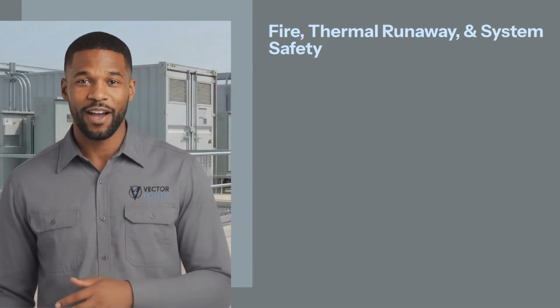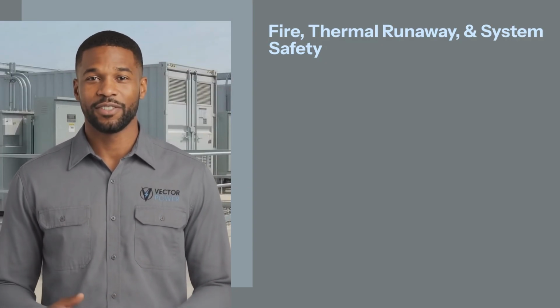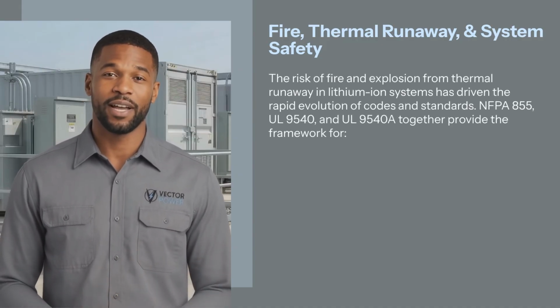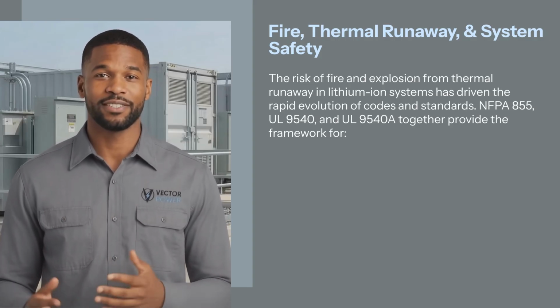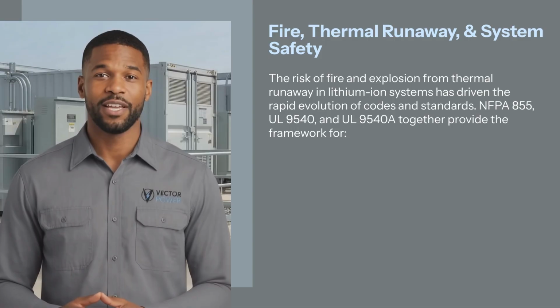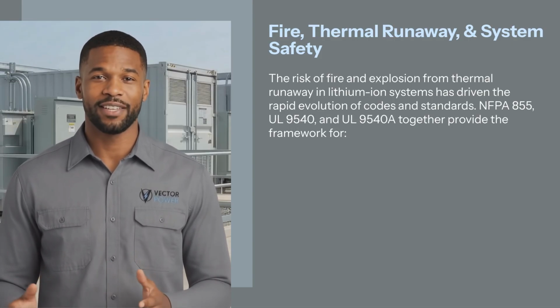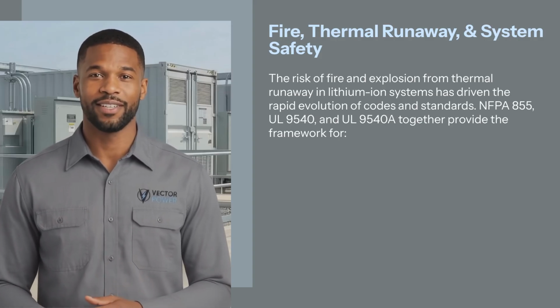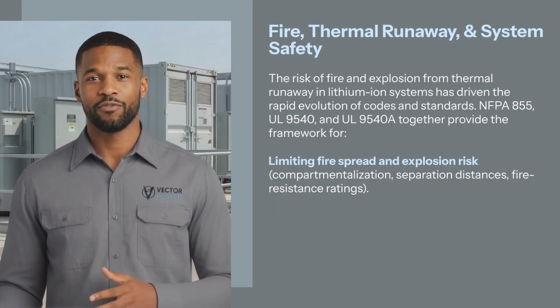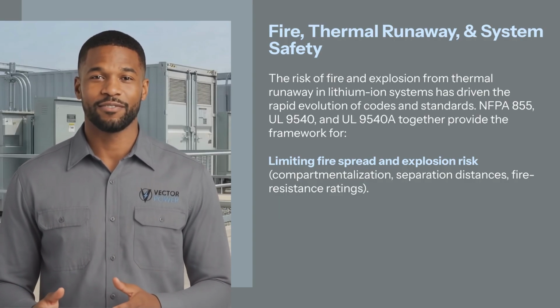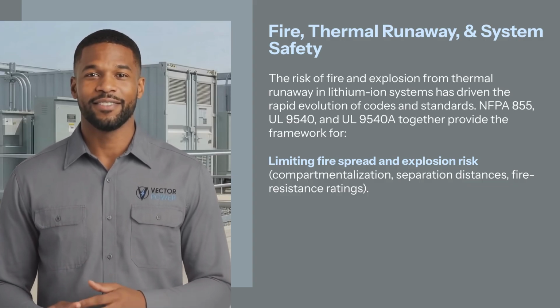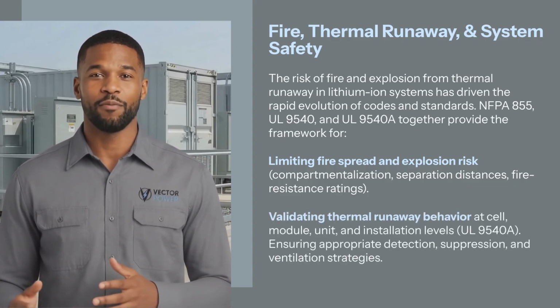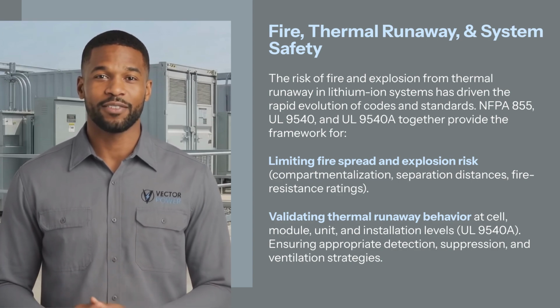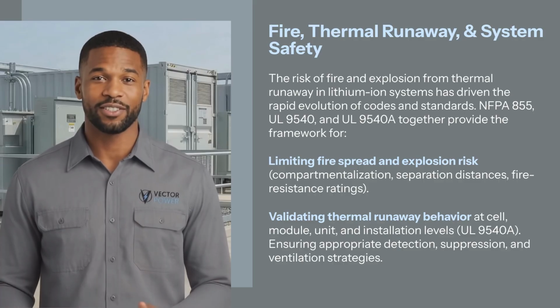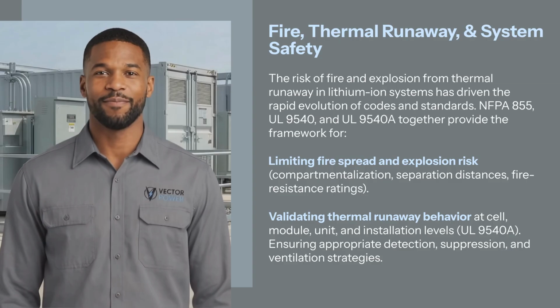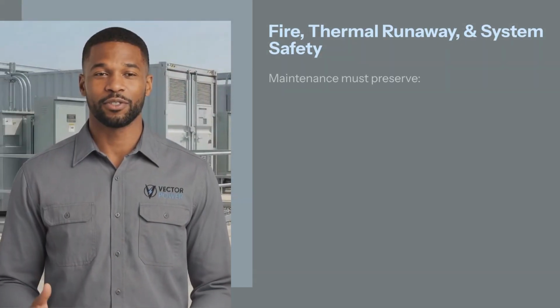Let's take a moment to address fire, thermal runaway, and system safety. The risk of fire and explosion from thermal runaway in lithium-ion systems has driven the rapid evolution of codes and standards. NFPA 855, UL 9540, and UL 9540A together provide the framework for limiting fire spread and explosion risk: compartmentalization, separation distances, fire resistance ratings, and validating thermal runaway behavior at cell, module, unit, and installation levels (UL 9540A), ensuring appropriate detection, suppression, and ventilation strategies.